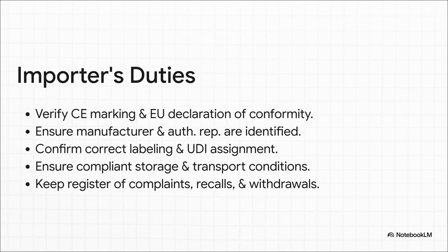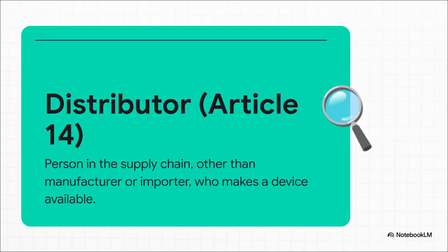You are the checkpoint. Before that device moves an inch further, you have to confirm the CE mark is present, the manufacturer is identified, and the labeling is correct, including its unique device identification, or UDI. You're also responsible for making sure storage conditions are right and for keeping a detailed log of any complaints or recalls. And finally, we get to the distributor.